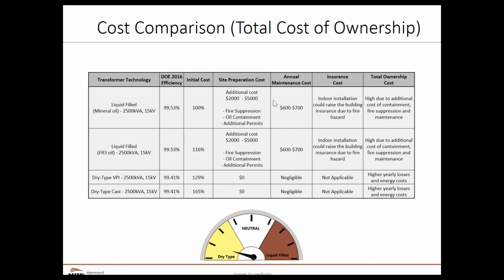But the other big thing is the site preparation. How is the site prepared? In order to take some of the advantages of the two designs, with liquid filled, I might have a lower initial cost for a transformer, but higher site preparation cost. With a dry type, I might have a higher initial cost for the transformer, but I might not have additional site preparation cost. And you have to be able to adjust both of those to achieve the full advantage of either design. In addition, there's additional maintenance cost.